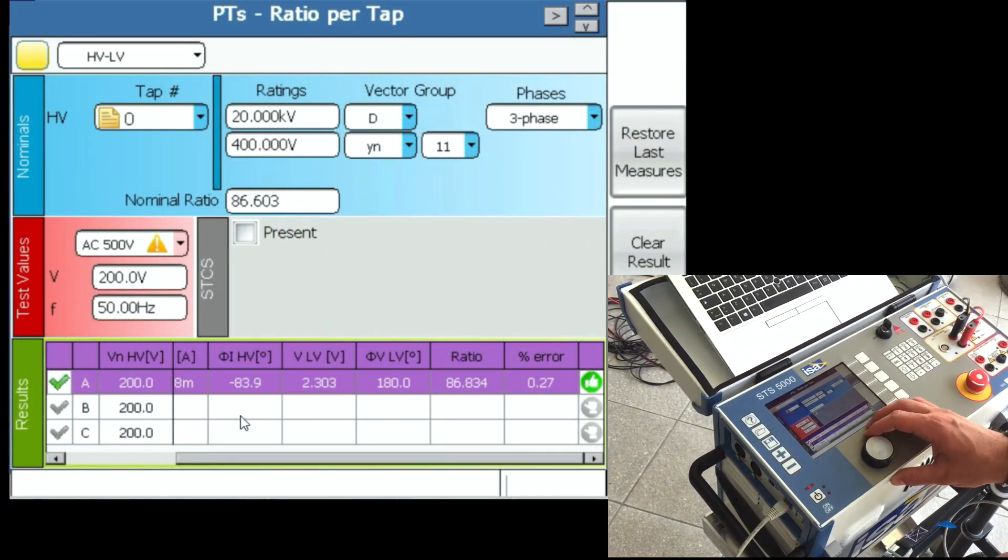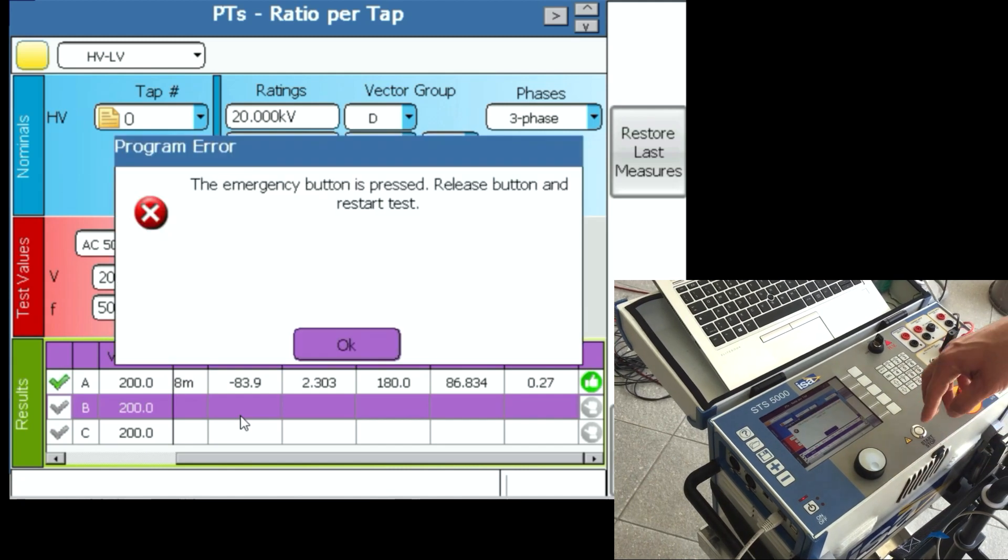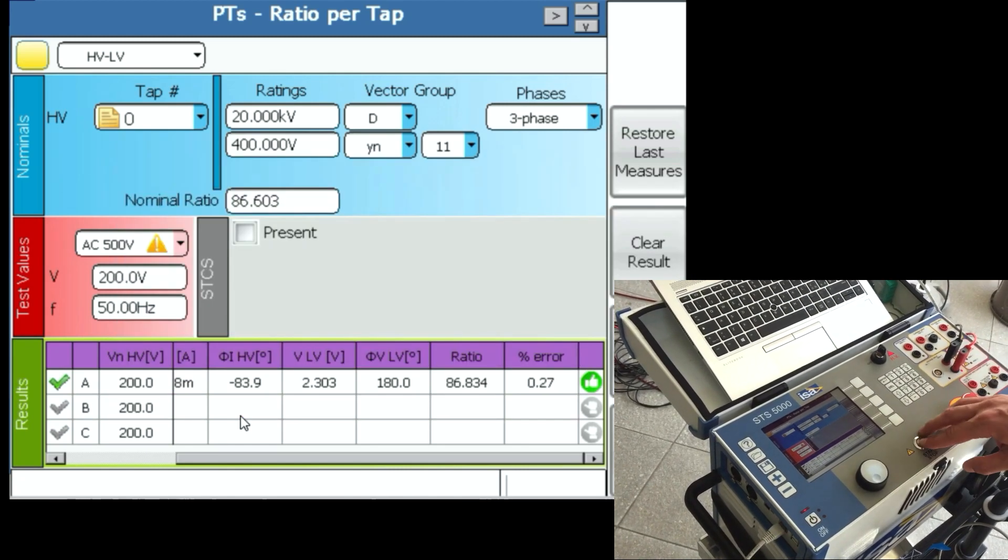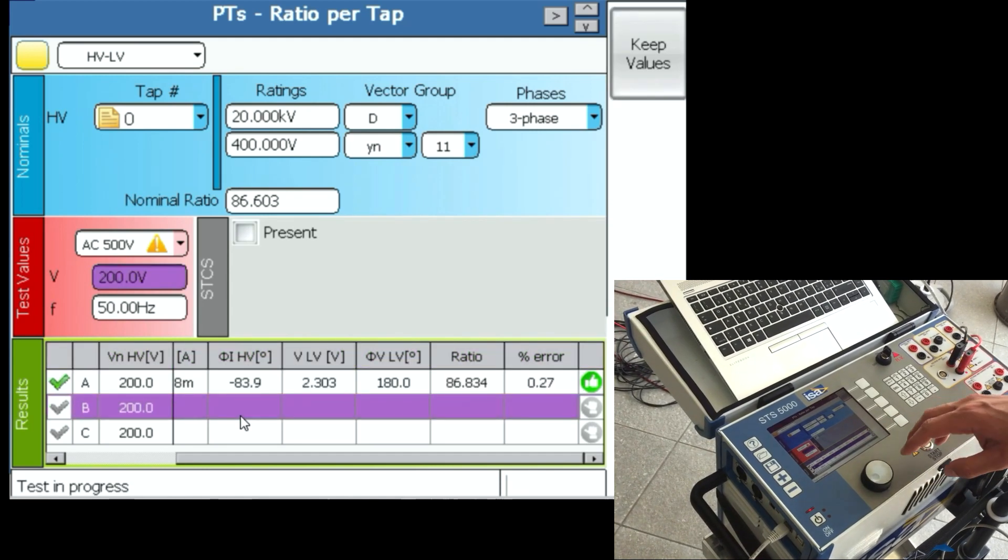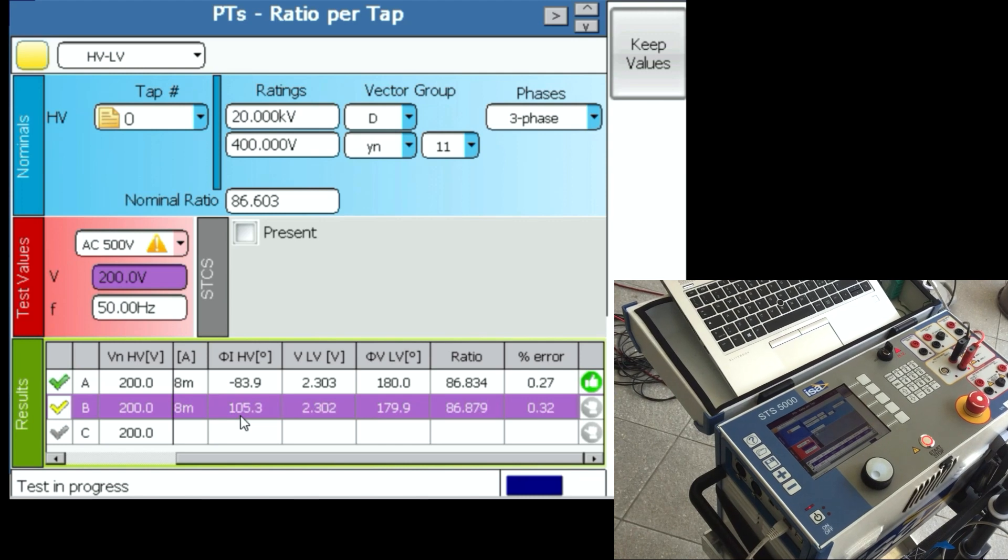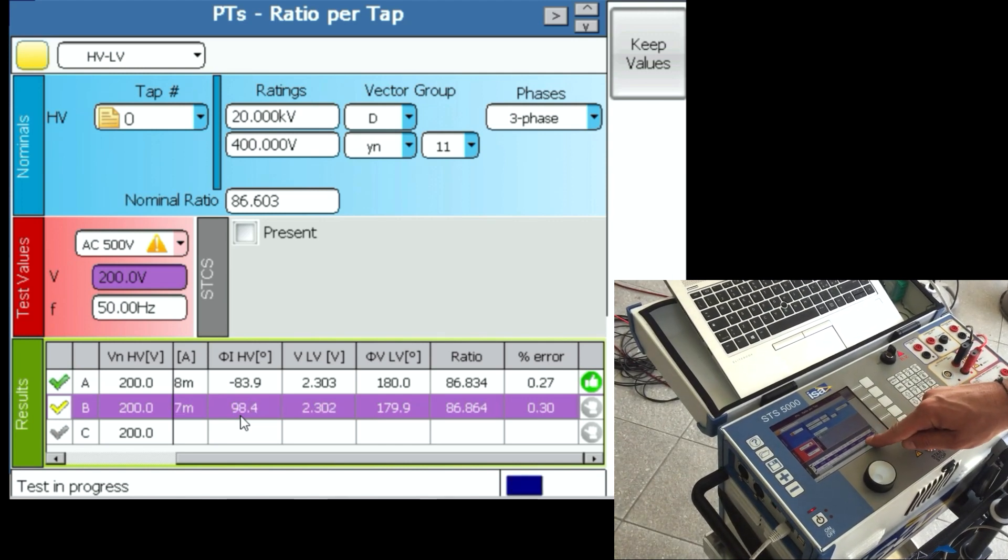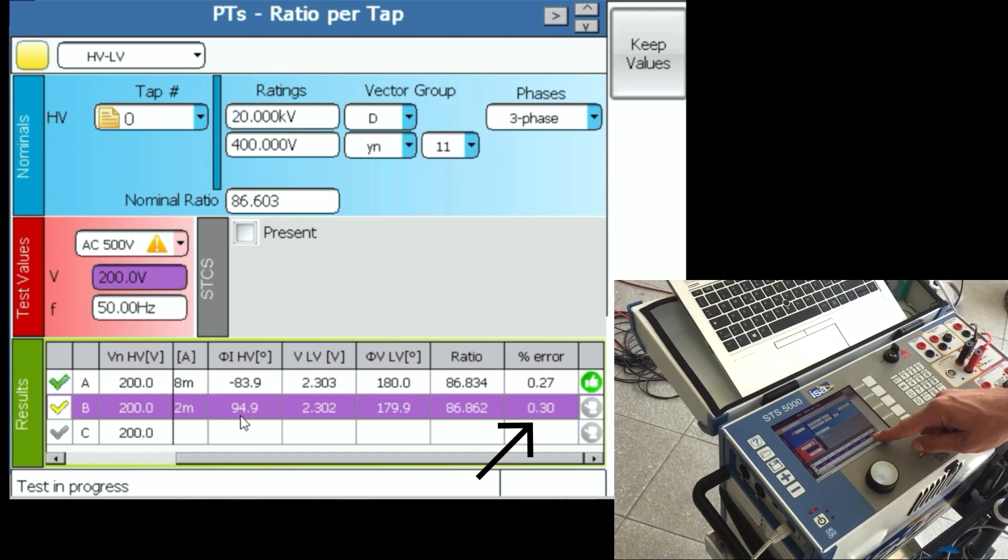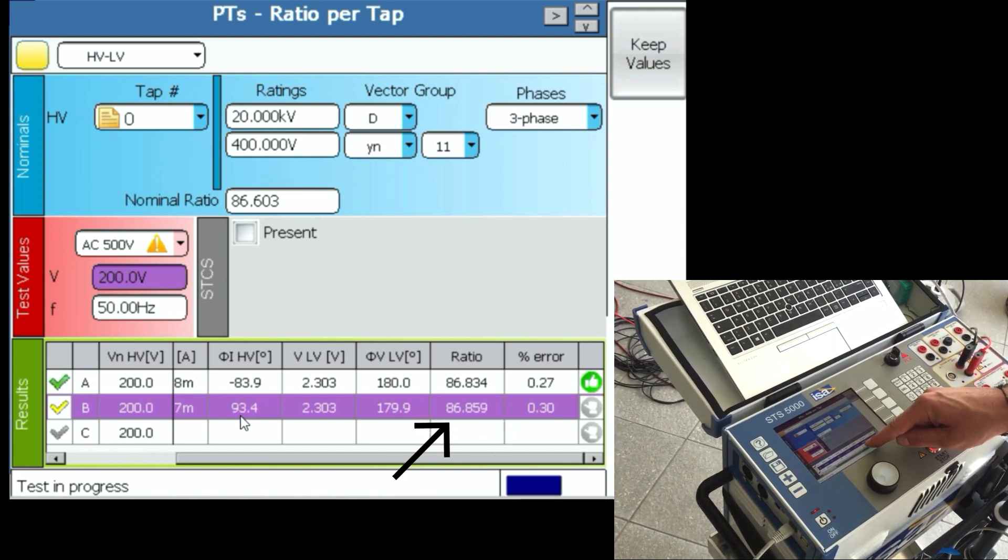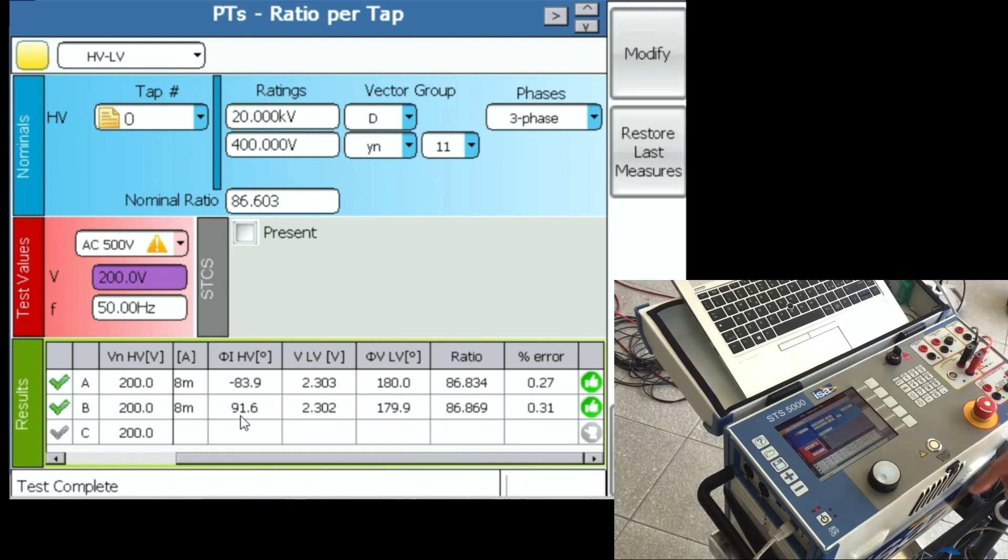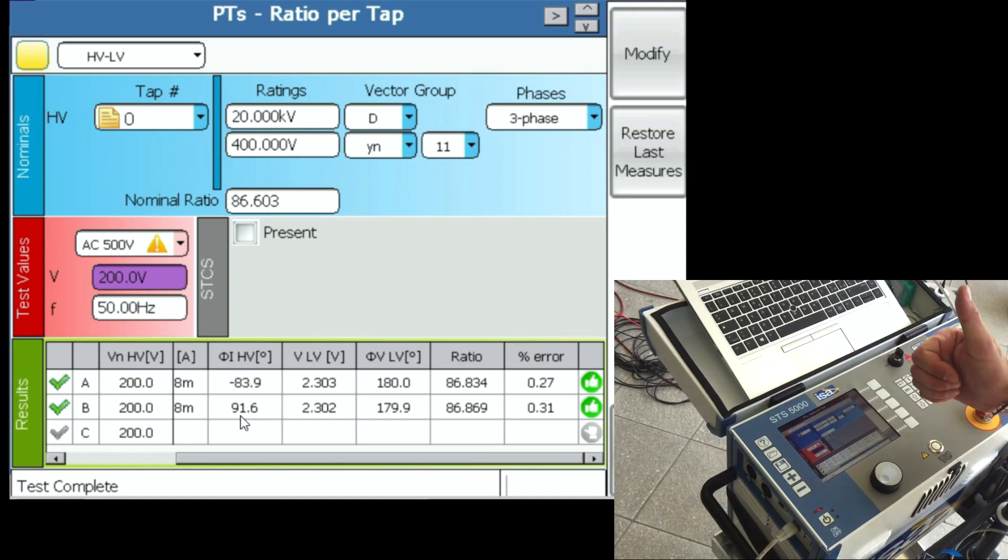And then I change the phase in STS and I press again start and I release. Because the emergency button is pressed, I have to release the emergency button and do this again. Now what we are seeing is that for phase B the error is 0.3%, the effective ratio is 86.8. And I press keep values. 0.31 is less than 0.5, green thumbs up.